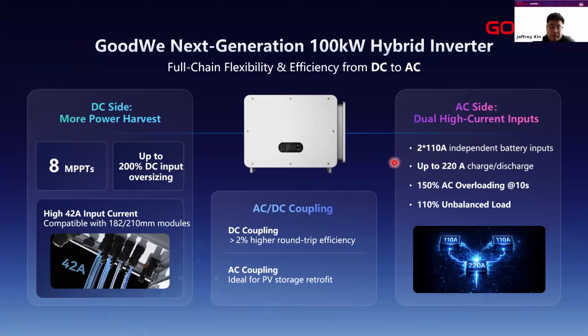So for our inverters, we can provide 10 seconds of 150% overloading for the off-grid output. That means if you connect an air conditioner or other inductive consumption, our inverters can easily support the startup of that inductive load.